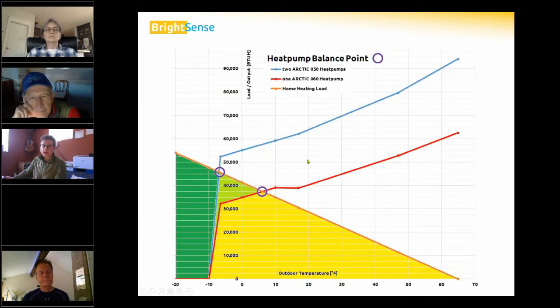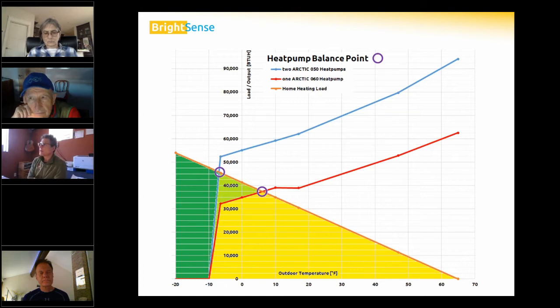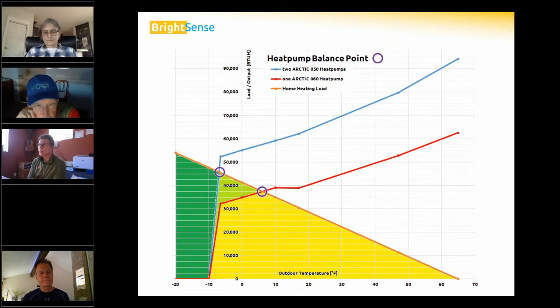Because our heat pump sits outside in the outside air, performance depends on outside conditions. The colder it is outside, the fewer BTUs are available to harvest, so heating output goes down. At the same time, our building's heating load goes up as it gets colder — these two curves oppose each other.